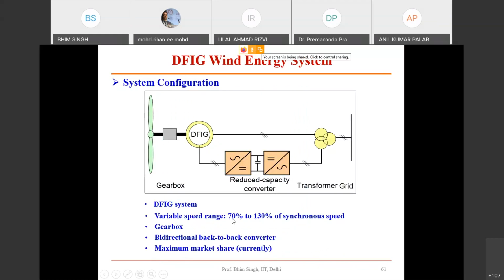The slip varies from plus minus 30%, with speed ranging from 70% to 130% of synchronous speed. For a 4-pole machine, which is normally used, at 50 hertz the synchronous speed is 1500 RPM. So 70% is 1050 RPM, and 130% is around 1950 to 2000 RPM. So 1000 to 2000 RPM is the typical speed range.